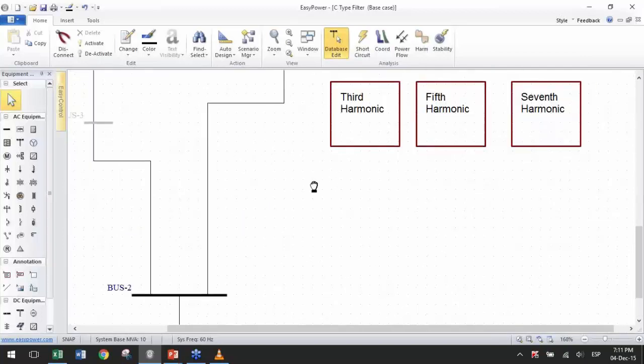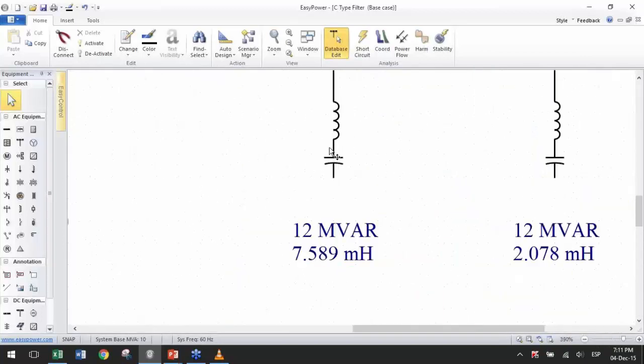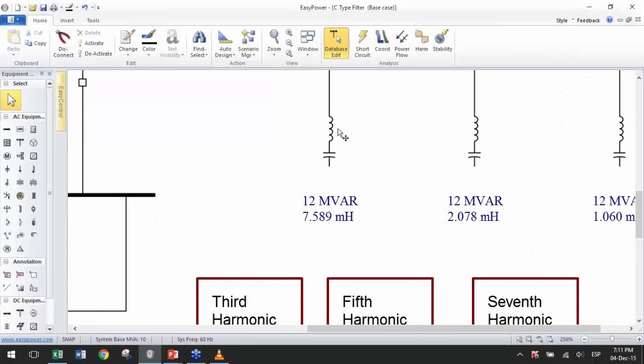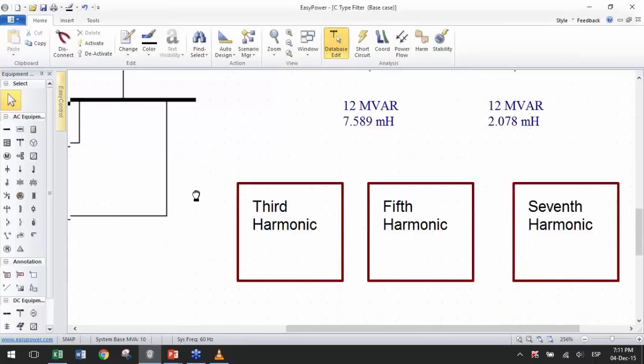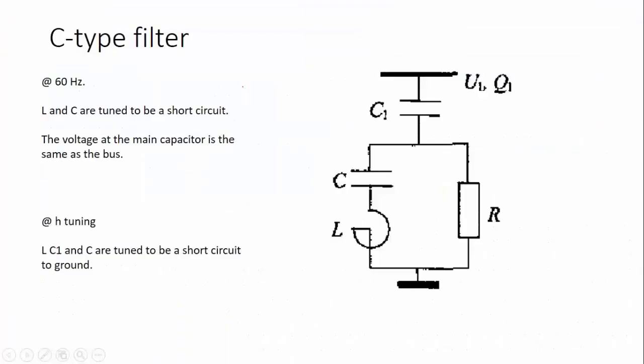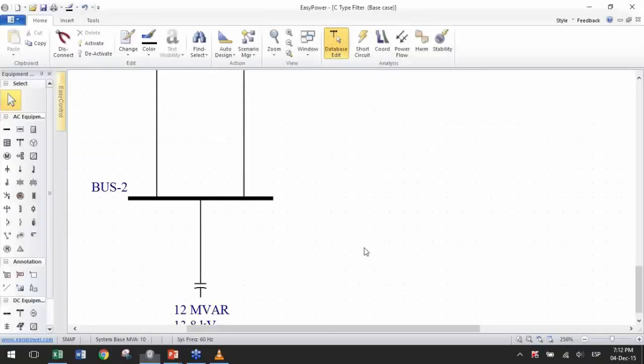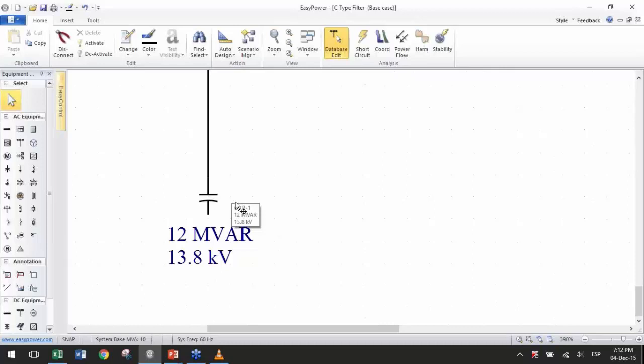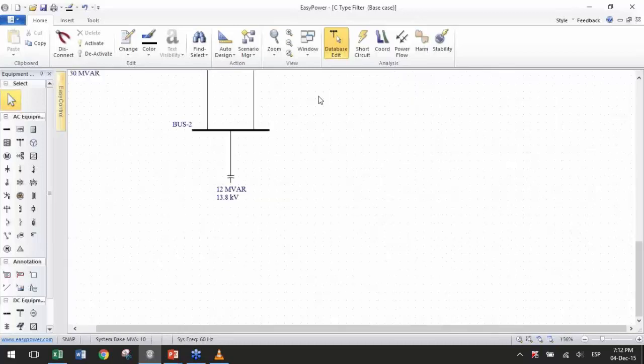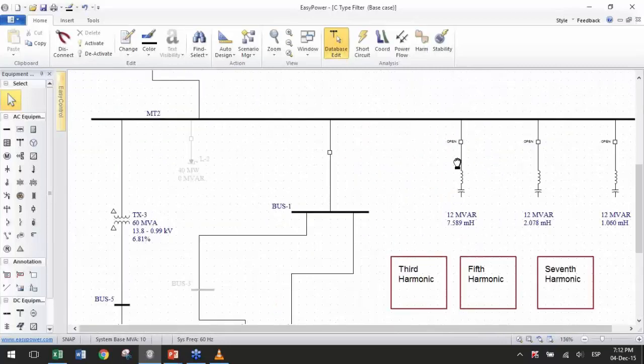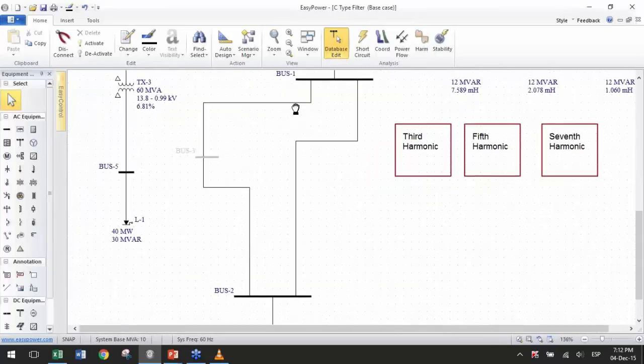Now, normally when you design a notch filter, the voltage here, the capacitor voltage, is much higher than the bus voltage because of the harmonic response from the inductor. In a C-type filter, because this is a short circuit, this voltage is the same as this one. So it's very easy to estimate the voltage for this capacitor. So I'm placing it at 13.8, which is the same bus voltage.